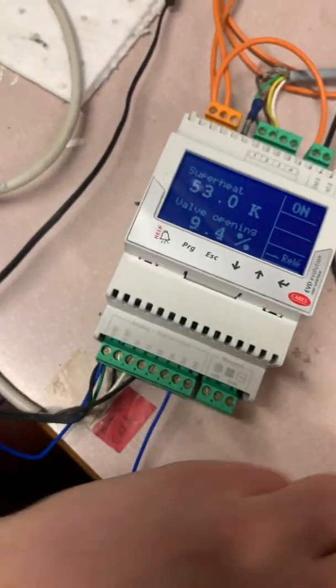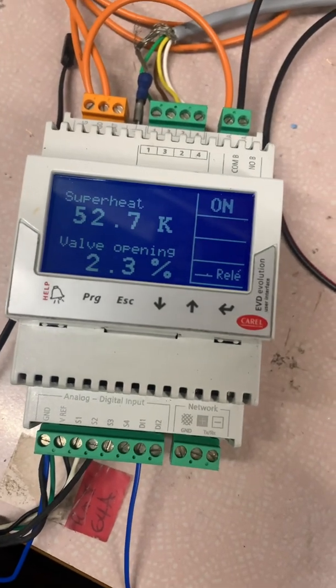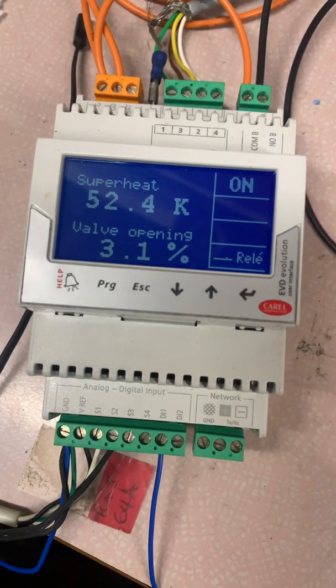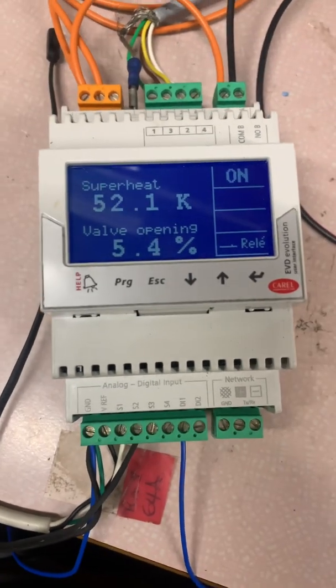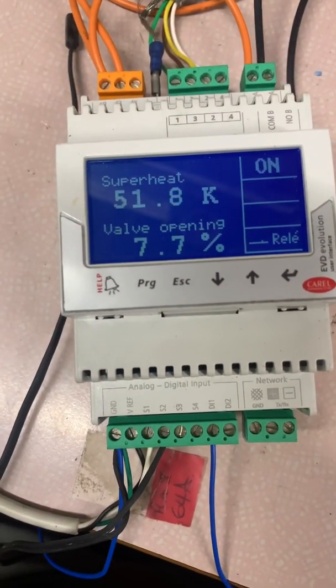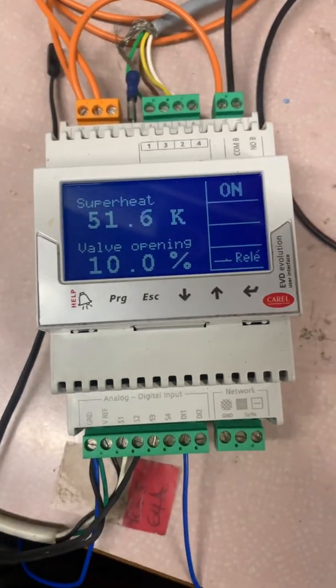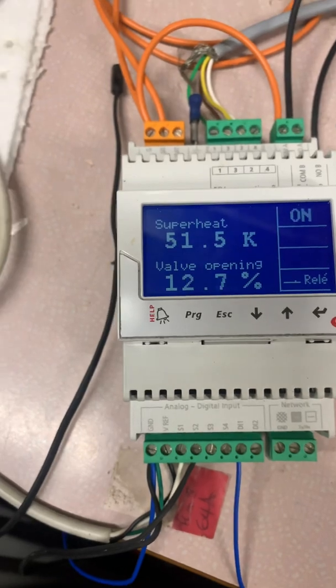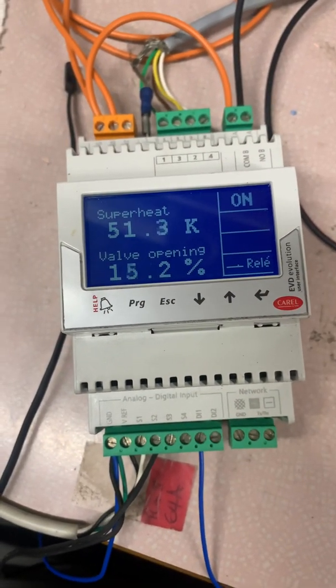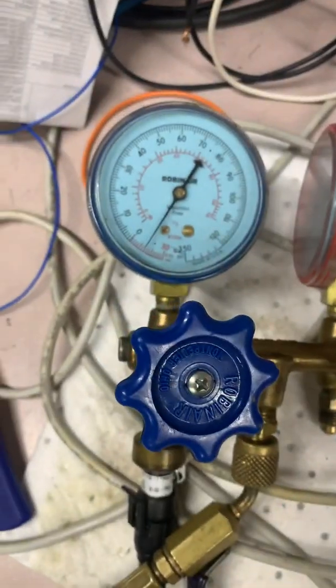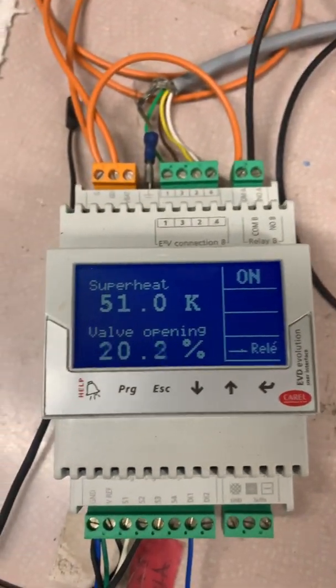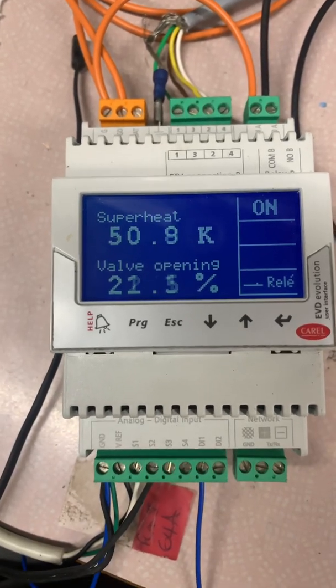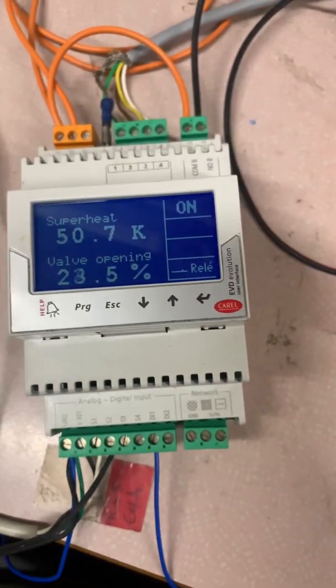The valve here, I can blow through it. So this is taking its time to open because there'll be a time delay in there, so it doesn't just whack open. Because there's a massive superheat now, because I've let the pressure out, so it thinks it's like zero psi, and it's more than 20 degrees on that probe, and we can go down the screen.